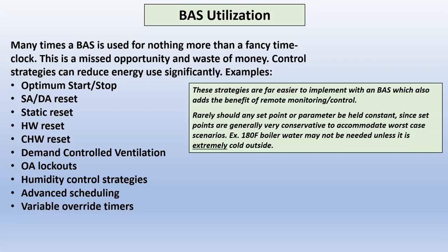Demand control ventilation. Why should I leave my outside air dampers open all the time when I may not need it? So this actually measures the CO2 in the building based on how many people are in there breathing, and it modulates that outside air based on that. And in hot, sticky South Carolina, where I happen to be, this is a big hitter. Big, because that hot, humid air, the latent load is really severe here.